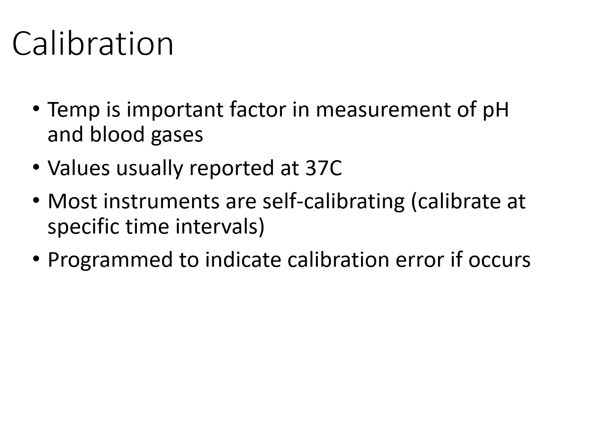Instruments are programmed to detect and indicate calibration errors, and if the calibration fails or values fall outside those acceptable limits, the device alerts the operator to avoid erroneous results. This feature helps to improve quality control and patient safety by ensuring only accurate measurements are reported.